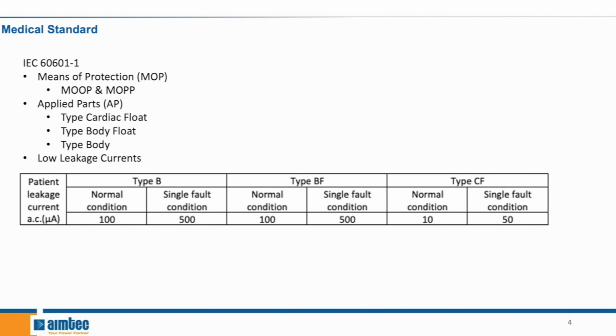So the cardiac float is connected directly to the patient's heart. For example, an artificial pacemaker or an automated external defibrillator. Next, we have the body float, and this is when there is a direct connection to the patient. For example, we have a ventilator or an ECG monitor. Finally, we have the body type, or type B, which is not in direct contact with the patient. And for example, we have intensive care beds or medical x-rays. And even though, yes, the patient is in contact with the machine itself or with the bed, there is no electrical connection between the two.